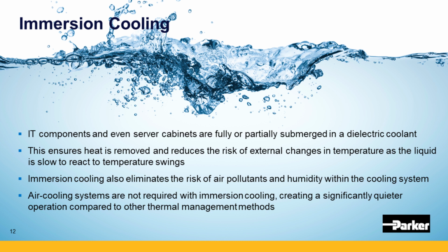Then there's the other style, immersion cooling. It's what it sounds like - you literally take a server blade or piece of IT gear and submerge it. Obviously you're not using water, that would be a bad idea. It's some sort of dielectric coolant - it can be an oil, sometimes highly fluorinated types of coolants. There are companies out there that specialize in these somewhat expensive fluids. This ensures all the heat is removed, so there's no risk of external temperature changes or other external factors. It really isolates and cools the entire piece of IT gear completely.